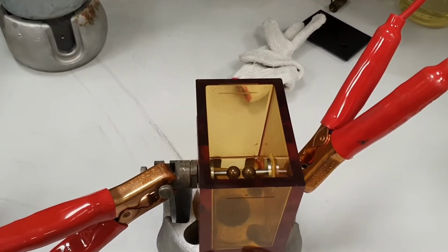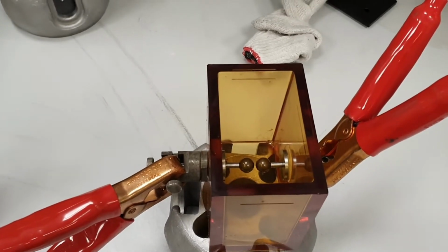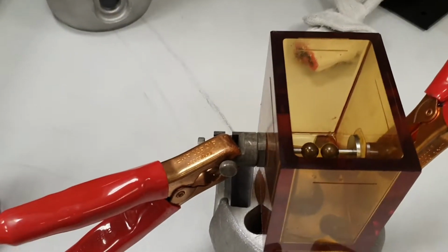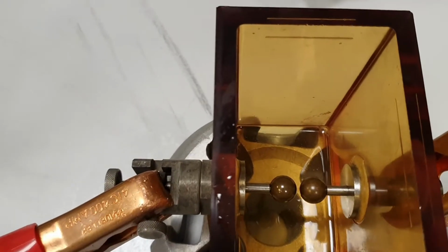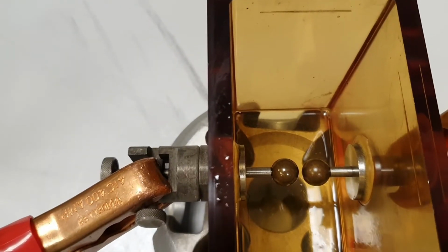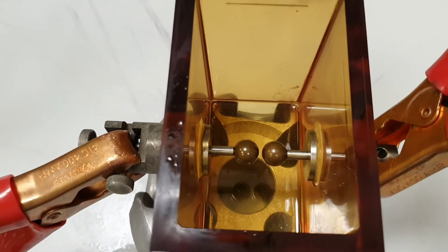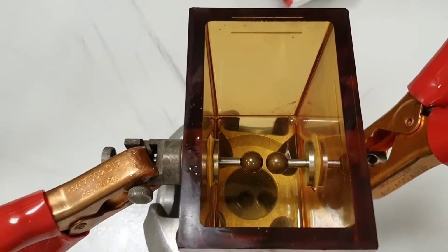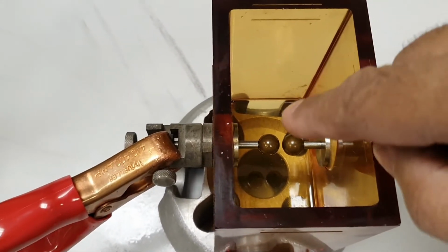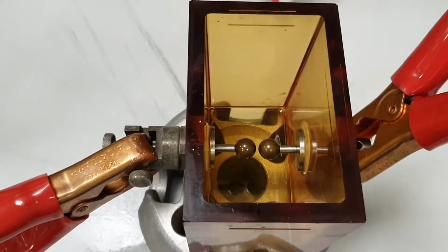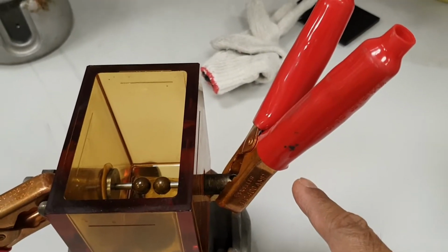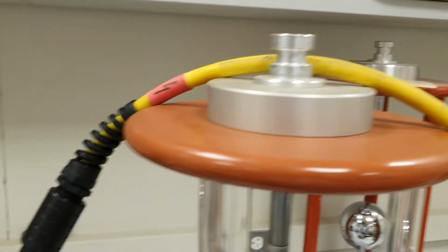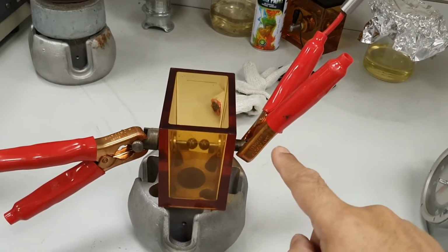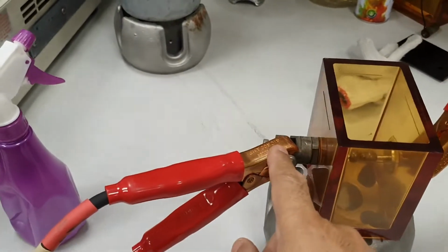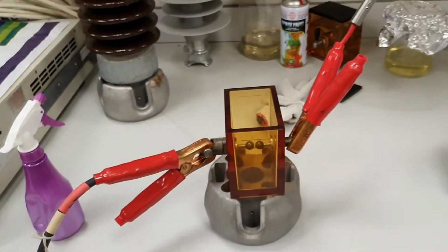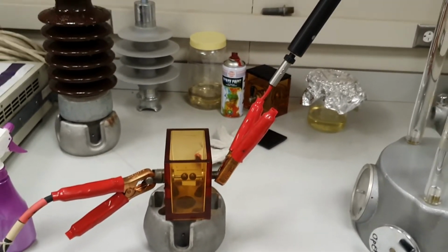Okay, the third part is testing of tan delta for an oil. So you have this oil test cell which has two spherical electrodes. The gap will be kept fixed at 2.5 millimeter. So first, for finding C0 for air, we'll keep this open, nothing inside this test cell. This is just the empty test cell, and we'll have high voltage connected to this part. So this is the yellow wire which I mentioned before. It is coming here and being connected at one electrode. The second electrode, the black wire from the instrument, will go there. So this is how your total setup is connected.